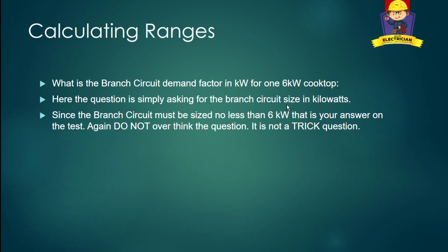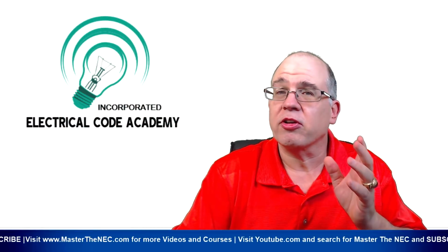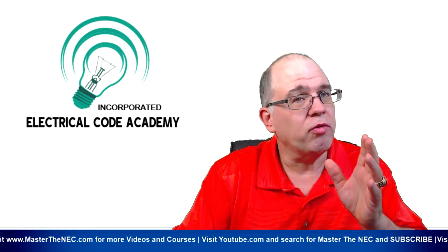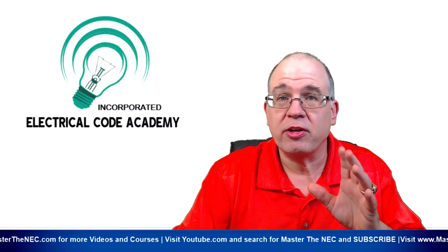Now, if it wants to know the actual ampacity, then you would take this 6 kW. Again, you would do it times 1,000. Or you just know that 6K means it's 6,000 watts, and you divide that by whatever the voltage is. In this case, let's say 240 volts. So then you would just take 6,000 divided by 240, and that's going to give your ampacity value. Okay, and that would be the answer to your question. All right, not a trick question. It's simply wanting you to remember that you want to simply answer the question as it's written. Don't overcomplicate it. Just simply take what you see on the question.